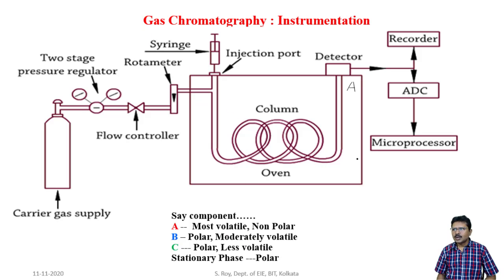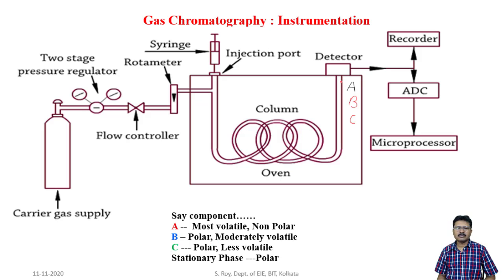So B will reach the outlet of the column after A, and C will reach after B. From this example we can say A will reach first, then B, then C at the outlet of the column. The detector will detect this signal, which ultimately will be indicated as the chromatogram, from which we can easily identify which one is A, which one is B, and which one is C as per the retention time and peak details.